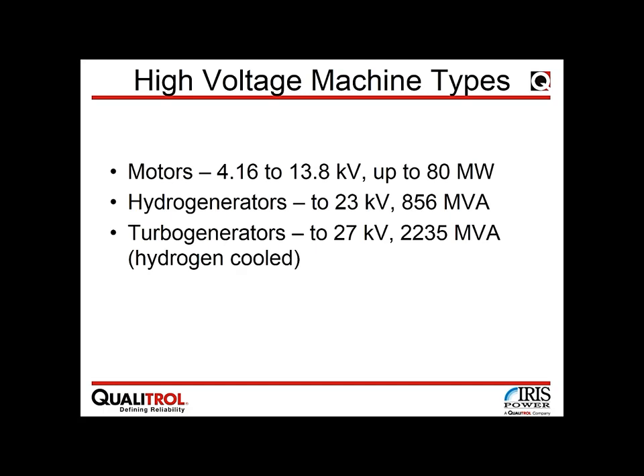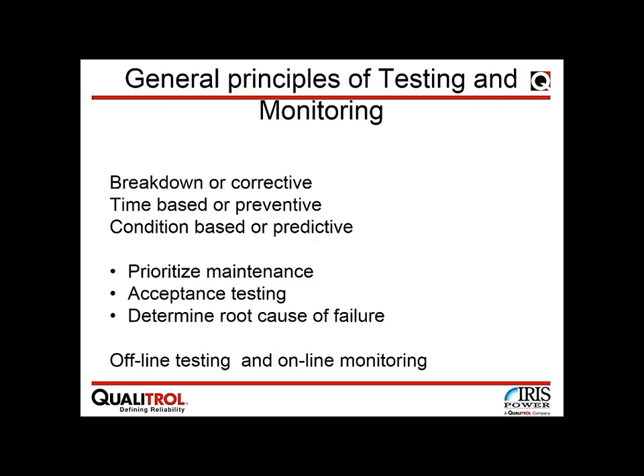Large machinery requires proper maintenance and care. Maintenance methods range from doing nothing — the breakdown or corrective approach, where you wait for failure — to time-based or preventive maintenance based on a calendar and manufacturer recommendations. Time-based maintenance is more proactive but still doesn't guarantee problems will be addressed on time or that the unit with the largest problem will be identified.